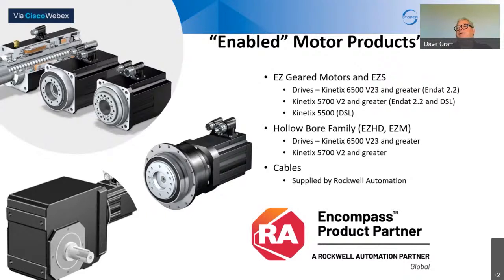So these are enabled motor products, if you would. They work with our standard EZ gear motors, and an EZS works on DSL. We're on the Kinetix 5500 platform with Stegmann DSL. We're on the 5700 platform with DSL. We can also do them in Endat 2.2, which will still work with the Kinetix 5700 and the 6500. We'll have a whole line of hollow bore motors we're going to show a little bit later. Those are Endat only. Stegmann does not make an encoder that will work in that motor. So those have to be used with 5700 and 6500.